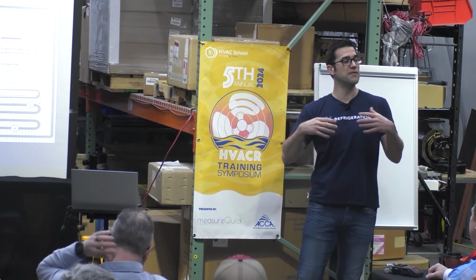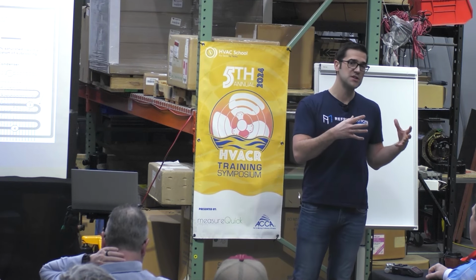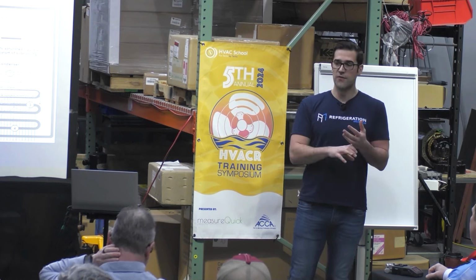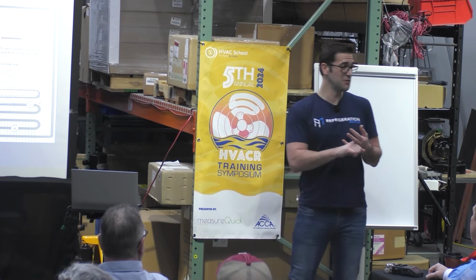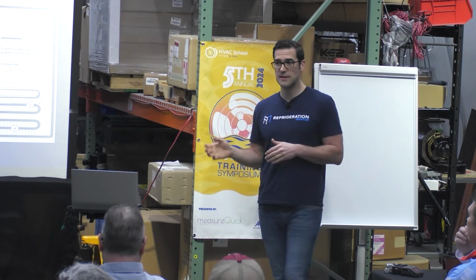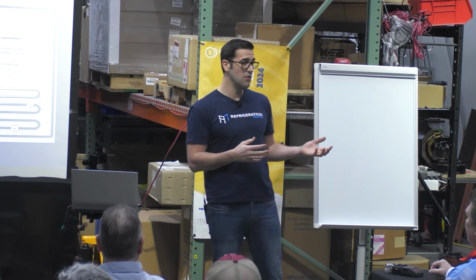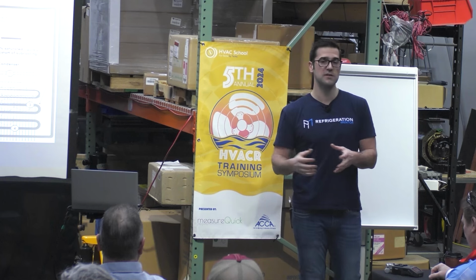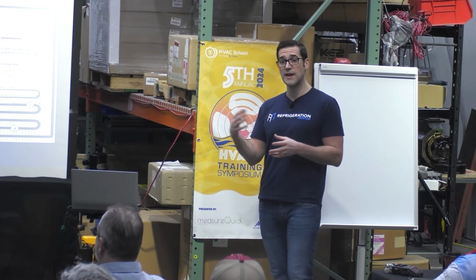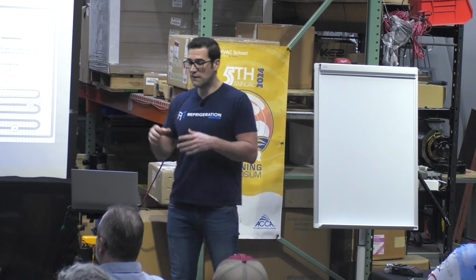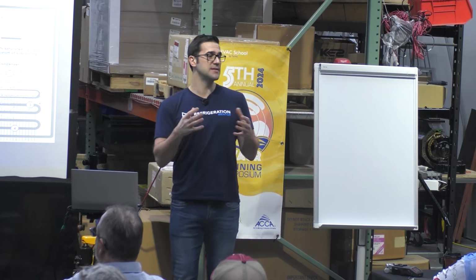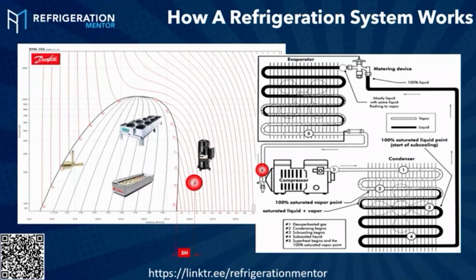What you need to understand, you're not going to use this in the field every day, but this is how you learn the fundamentals, especially when you transition from what you're working on today, 410, if you're still working on old school R22. All these refrigerants are being delisted or phased down or phased out. So you really want to understand that transition into the new A2Ls or A3s or naturals like CO2. But the first step of understanding how a system works is going to a basic system. So right now, if you work on residential AC, commercial HVAC, commercial refrigeration, every system works like this.